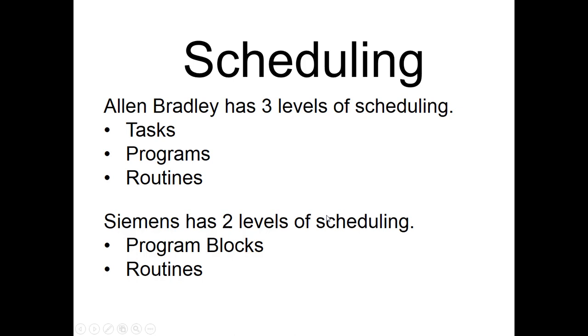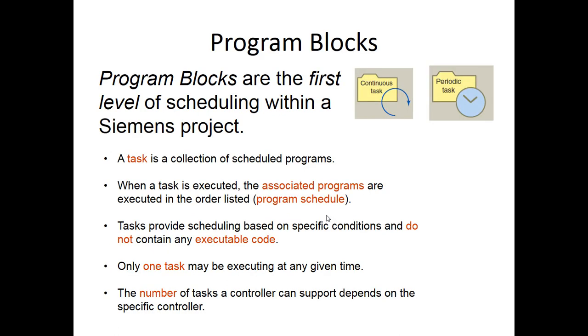When we talk about scheduling, Allen-Bradley has three levels: tasks, programs, and routines. Siemens has two levels: program blocks and routines. Basically we want to understand the difference between continuous tasks and periodic tasks. Some things are scanned continuously — the PLC just starts taking a look at the program block you've put in there, processes it, moves to the next one, and so on. These continuous tasks typically have pretty low priority.